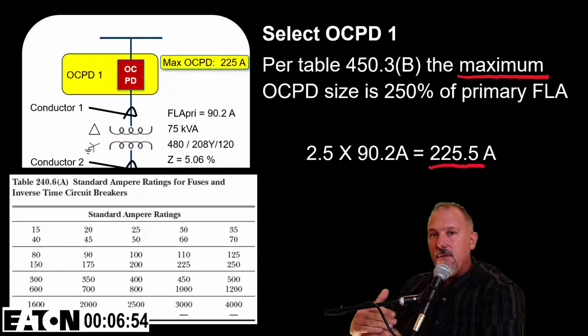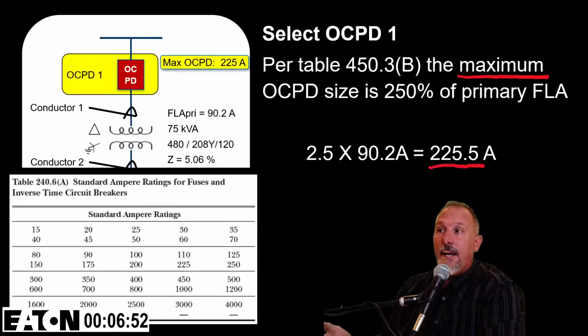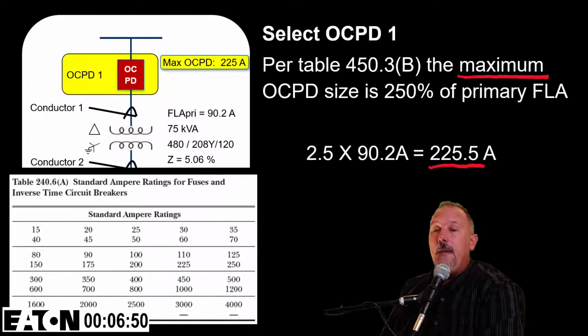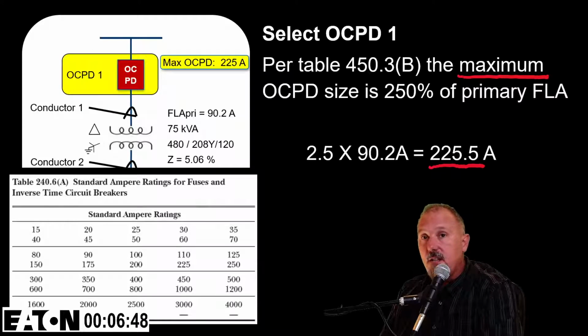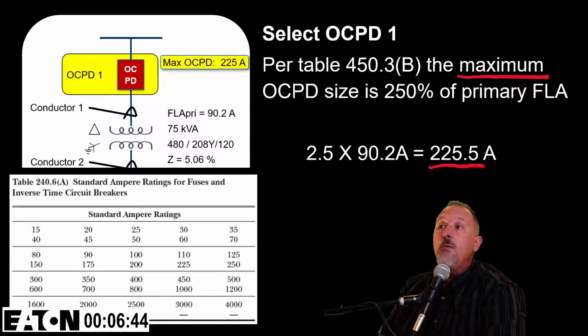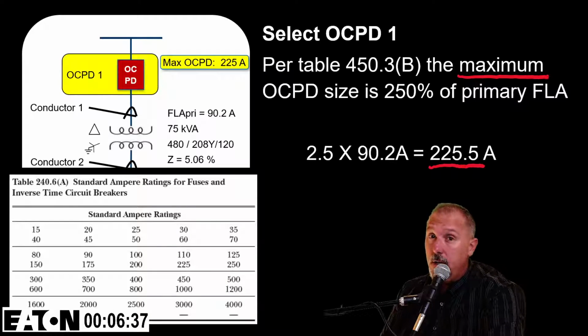I've got to come down to the next lower. In this case, I'm going to say that my maximum size primary overcurrent protective device is going to be 225 amps. The only time I would probably get into 225 amps is A, if I want to push that transformer really hard, I could possibly, again, reduce the life cycle, etc. Or B, if I'm selectively coordinating through that transformer.